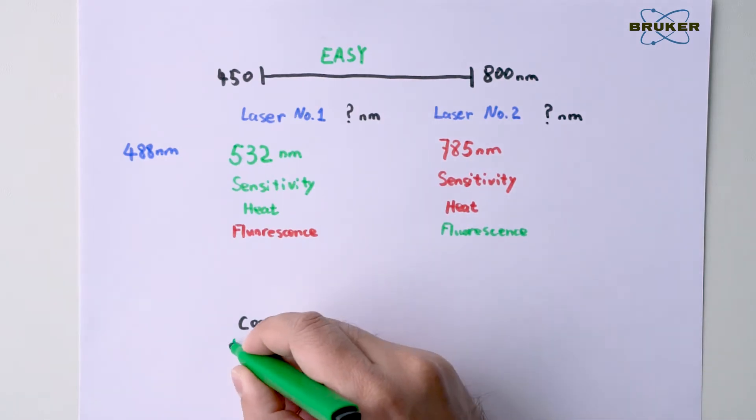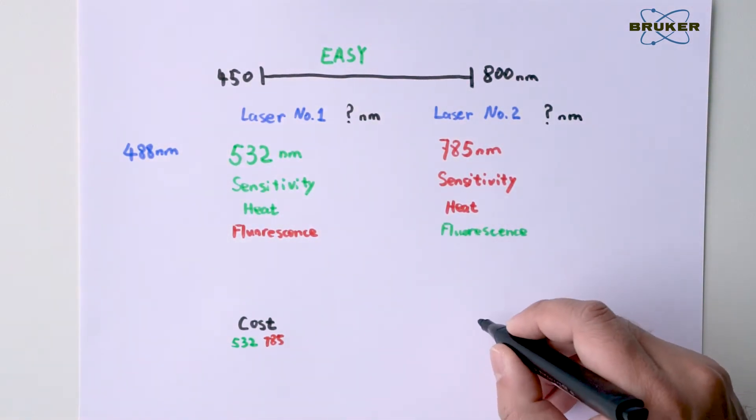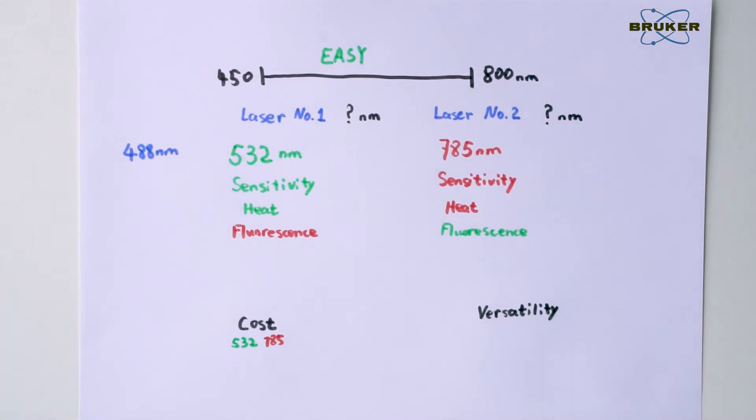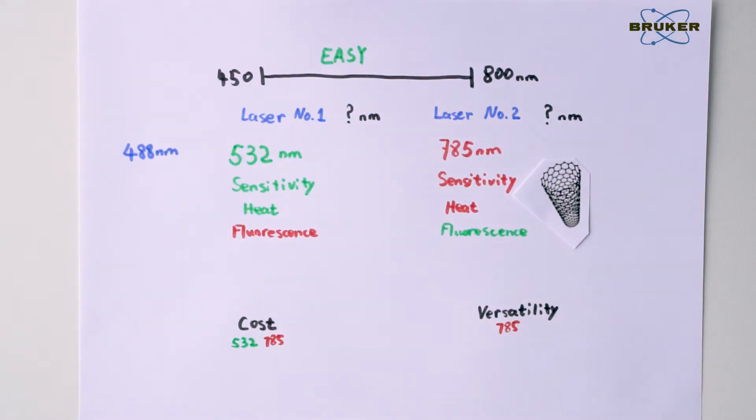Of course, carbon nanotubes can still be investigated by a near-infrared laser, but you will have to turn down the laser power and extend the measurement time. For organic and colored samples, however, a 785 nm laser offers a much more balanced performance with less fluorescence.